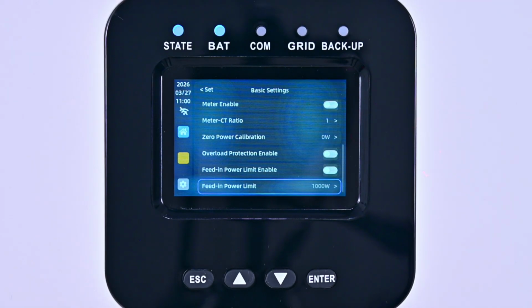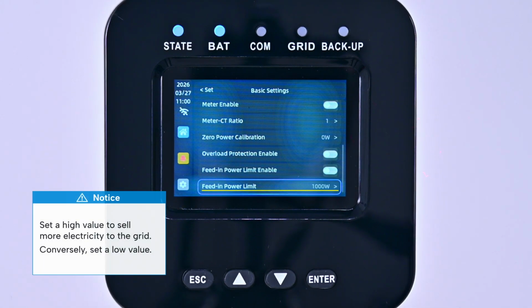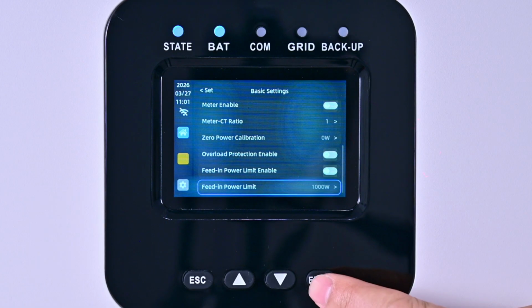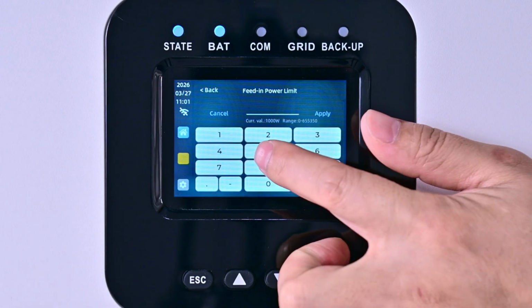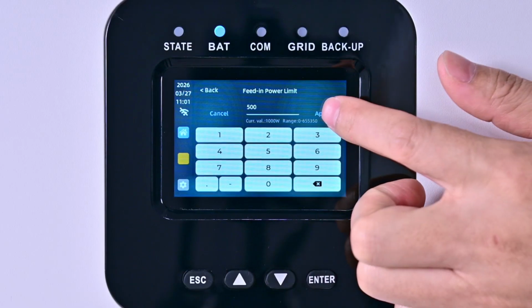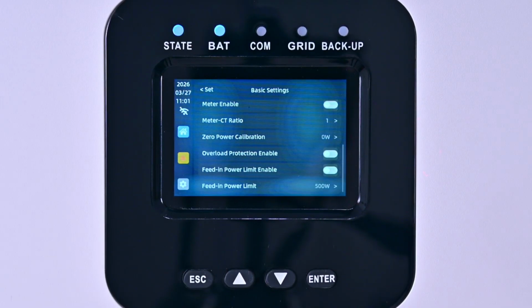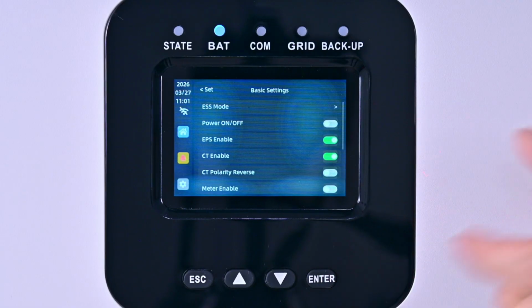At the bottom of the interface is a power feed-in setting. This represents the maximum power value that the ESS device can sell to the grid. If you have ample power, you can set a higher value to maximize revenue. Conversely, if you prefer to use more solar power, set a lower value. Here, we will set it to 500 watts. Once all these settings are configured and you confirm no further changes are needed, enable the Power On-Off function.